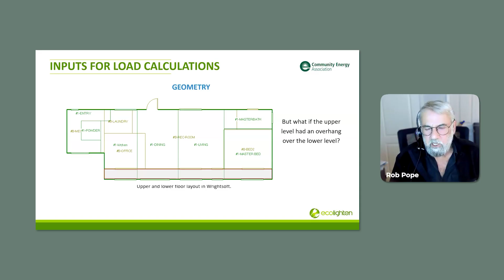Well, let's see. This is a 3D screenshot from the same program - you can see where the overhang is here. Without the overhang, we know what the loads are: 35,525 for heating, 16,175 for cooling. Look what happens if we put that little extra couple feet of overhang on the upper level, creating a bit of exposed floor in each room - we end up with a 38,000 BTU load instead of 35,000. So there's a 3,000-plus difference, and it goes up a bit in cooling too, to 17,000.